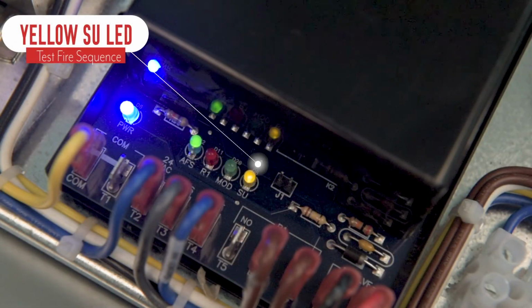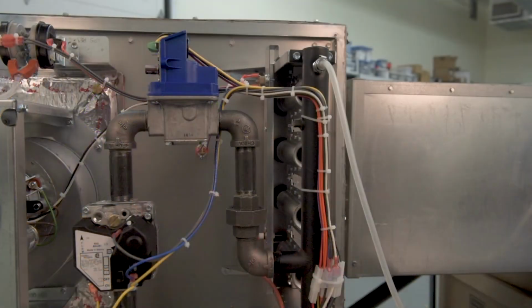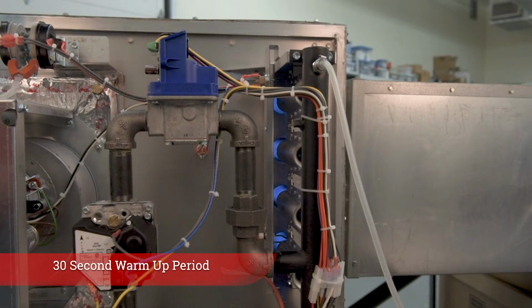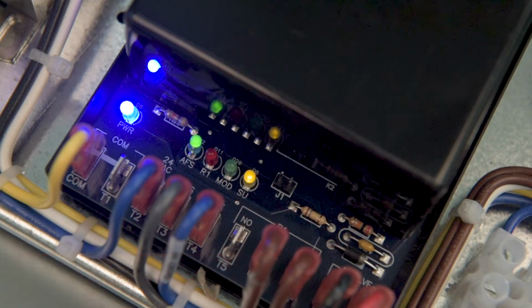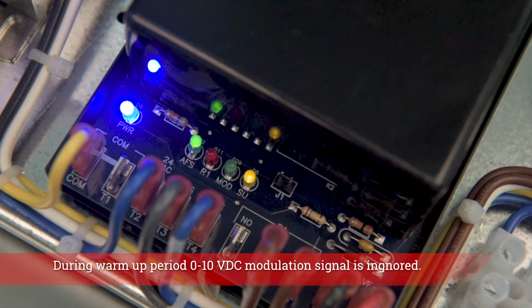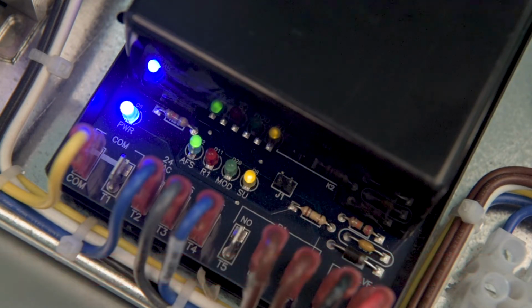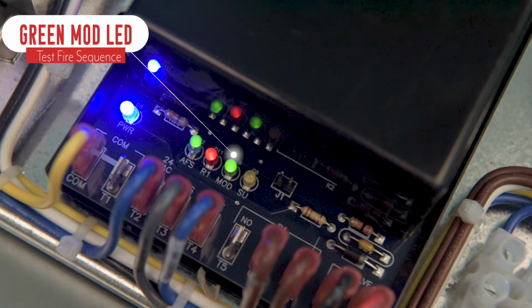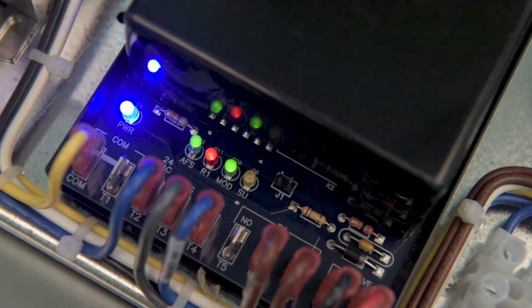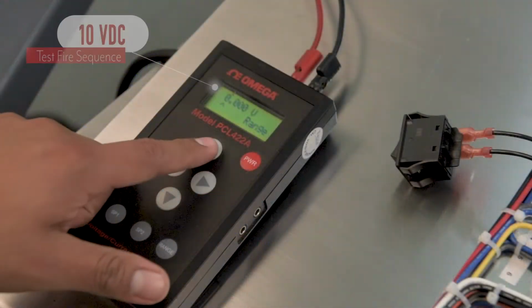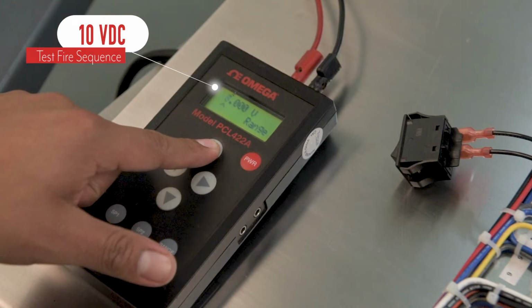The yellow SU LED, gas valve, and spark igniter are energized and the burners cross light. The heater continues to run with high-speed fan and the burner at mid-fire for a 30-second warm-up period. During this period, the 0 to 10 volt DC modulation signal is ignored. After the warm-up period has expired, the yellow SU LED will turn off and the green mod LED will turn on. The modulating valve will then move to the operating position specified by the modulation signal. Supply 10 volts DC to the SC40.